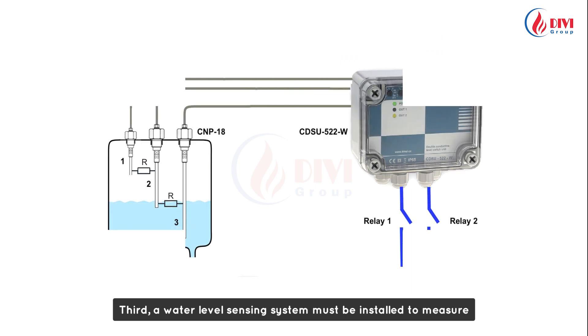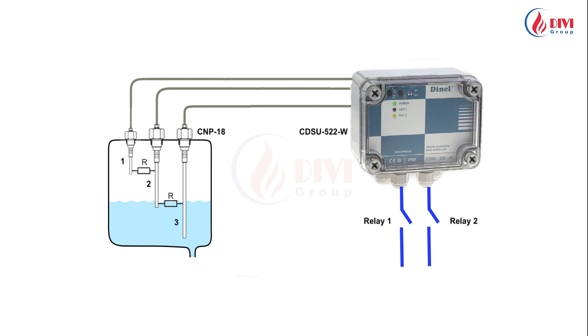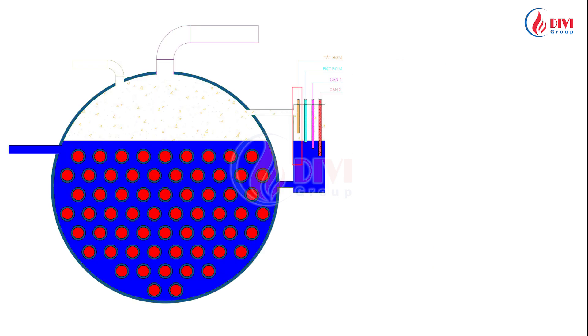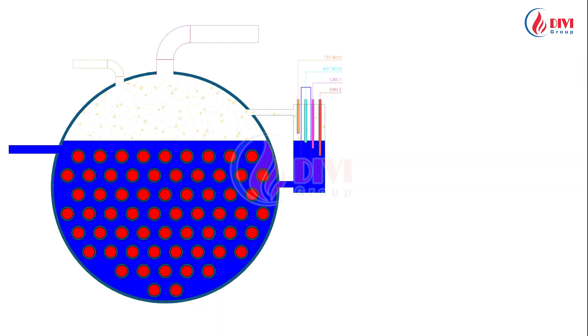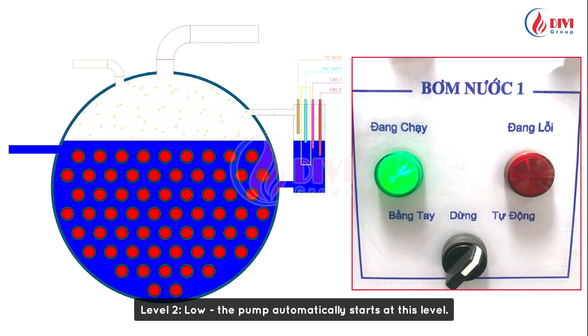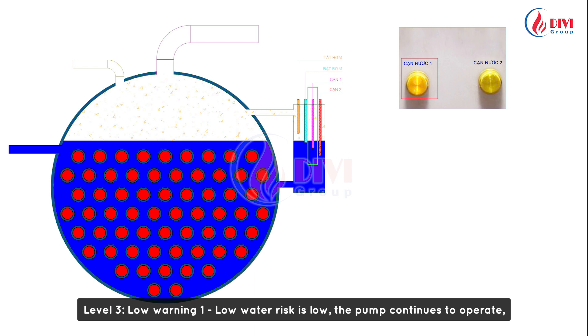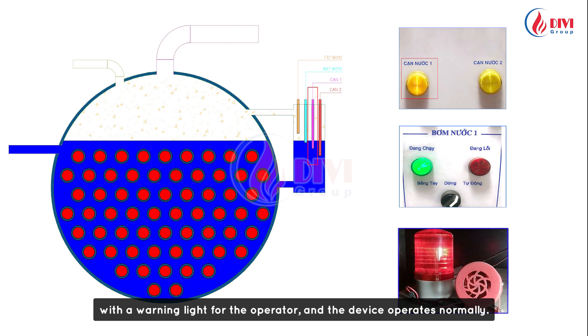Third, a water level sensing system must be installed to measure and warn about the boiler's water level. Water level sensors can be probe-based, with additional float-type sensors installed. Water level sensors are divided into four warning levels: Level 1 (full) — the pump automatically stops; Level 2 (low) — the pump automatically starts; Level 3 (low warning 1) — low water risk is low, the pump continues to operate with a warning light for the operator and the device operates normally.